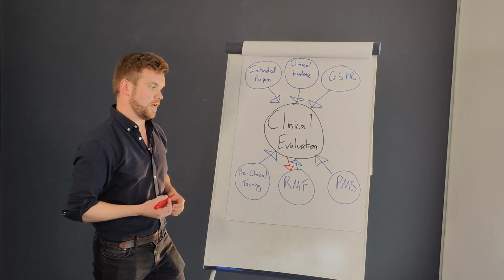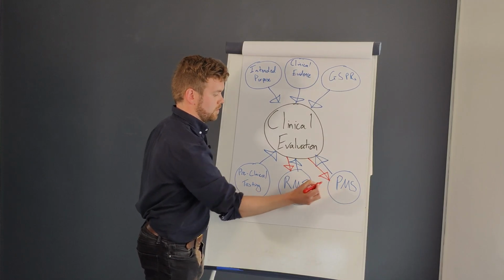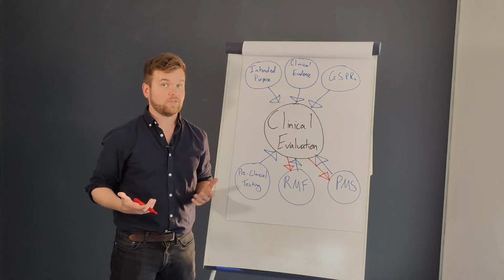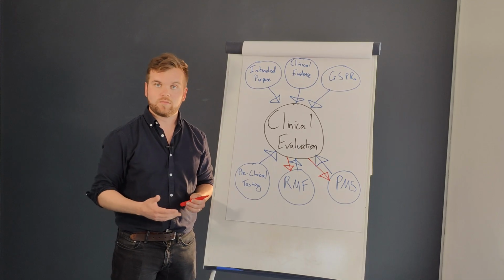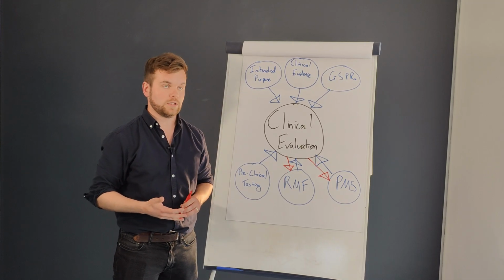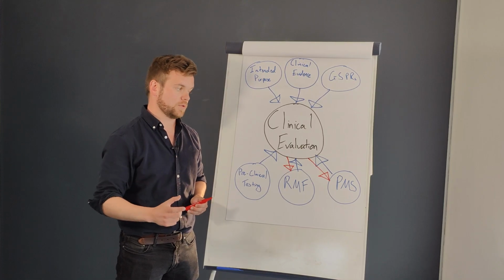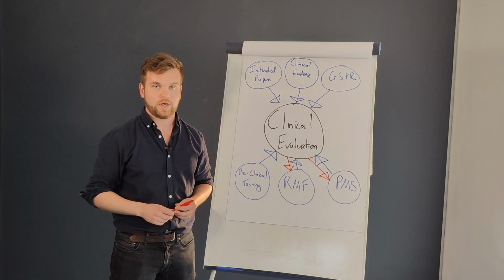And then the clinical evaluation will also feed into your post-market surveillance. So any areas of ambiguity at all in your clinical evaluation don't have to be disasters. You can use your post-market surveillance activities, post-market clinical follow-up or vigilance searches, for example, to address those and show that you're continuing to assess your device's performance and safety profile well after your current clinical evaluation.